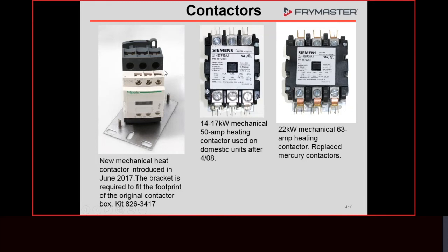So whether this new contactor was the real savior—since it does seem more robust—or it was the fact that we cut back on how many times they cycle, together the lifespan of our contactors has greatly improved. But considering these contactors are going into fryers that didn't necessarily have the software upgrade, this contactor is probably just working out to be better on its own. In combination with new equipment, less cycling plus new contactors, our issues with contactors have pretty much gone away.